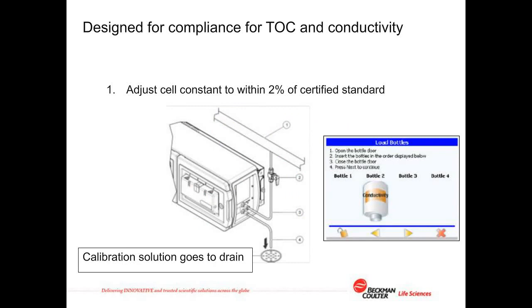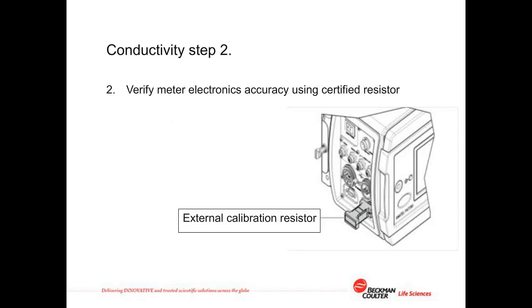Not only is this analyzer compliant for TOC requirements, but it can also be fully calibrated to USP requirements as a conductivity meter too. The cell constant can be checked using a certified conductivity solution, and the meter accuracy can be verified against a resistor of known certified value.